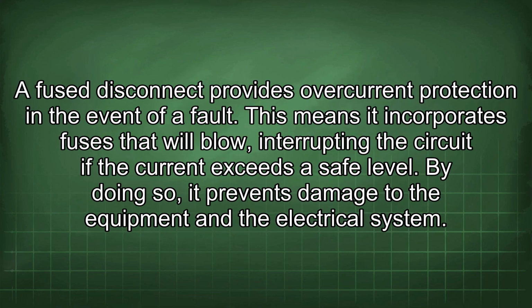A fused disconnect provides overcurrent protection in the event of a fault. This means it incorporates fuses that will blow, interrupting the circuit if the current exceeds a safe level. By doing so, it prevents damage to the equipment and the electrical system.